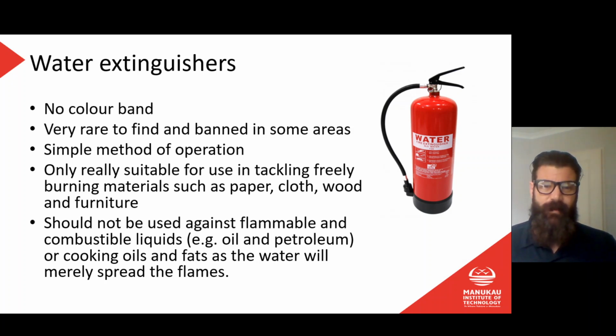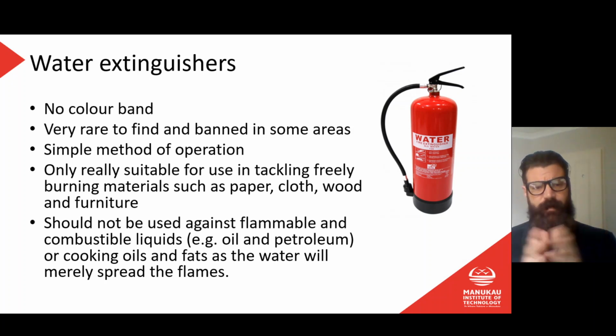Yeah, so the water ones are not really an effective option, right? We're definitely not going to use them against oil and fat fires for exactly that reason. The oil will float on the water and it goes everywhere. And then secondly, we're not going to use them on electrical fires because, as I said earlier, that will create an additional hazard. It might put the fire out, but we'll have water in our switchboard, water flowing everywhere, and that water being a conductor that could be live. So we may save ourselves from the fire and then end up electrocuting ourselves. So for a water extinguisher, if you've got a fire in a rubbish bin or something like that, it's probably not too bad. But you can still use a dry powder or a CO2 extinguisher against those kinds of fires too. So water fire extinguishers are fairly rare, as it says there. We don't often use them. In fact, I can't tell you the last time I came across one. Certainly by far the most common are going to be your CO2 and your dry powder, and in fact dry powder is a lot more common than CO2 as well.